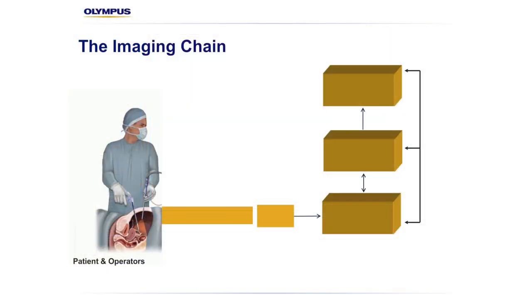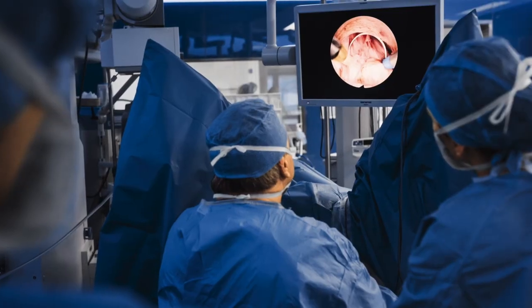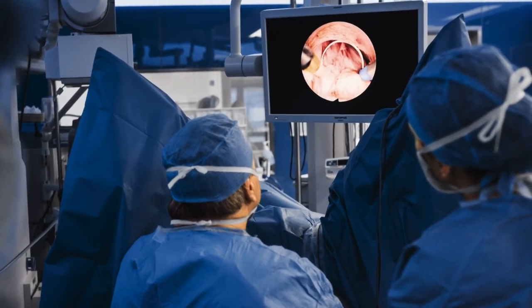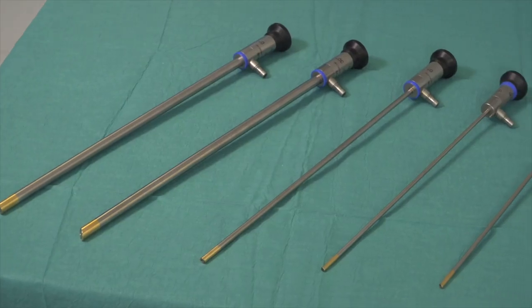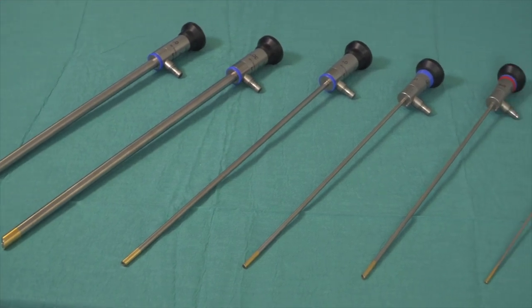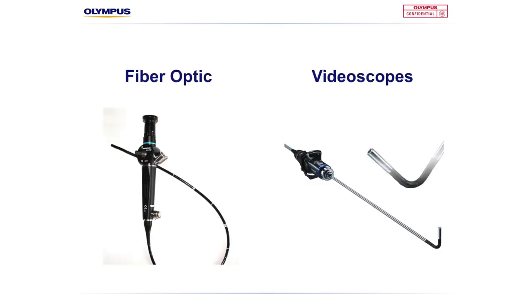For the first component of our chain, let's start at the patient end with the imaging instrument that comes into direct contact with our patient — the telescope. The telescope is the first component of our surgical imaging chain. It is a tool used to observe an object from an appropriate distance and relay the image to the observer in a practical way. The typical type used in laparoscopic surgery is a rod lens telescope, but there are also fibre optic and video scopes, each with their own advantages and disadvantages. For more in-depth discussion on the different types, please see the Olympus Imaging Three Types of Scope video.